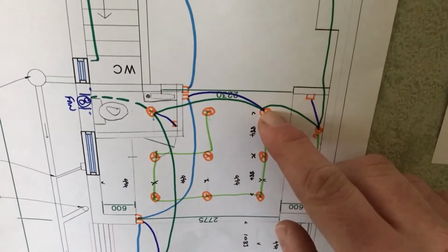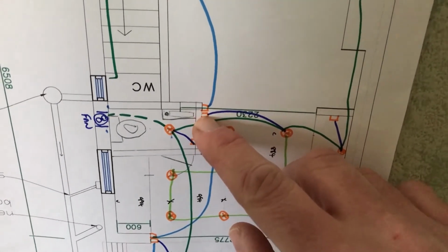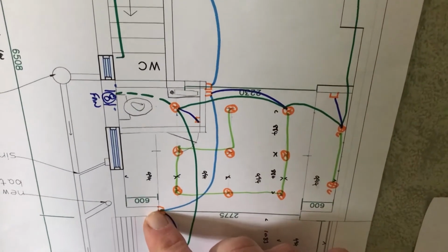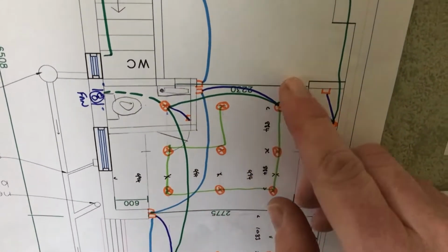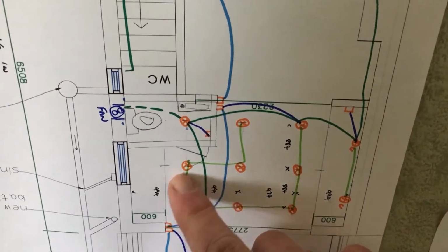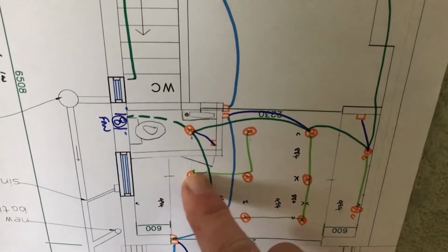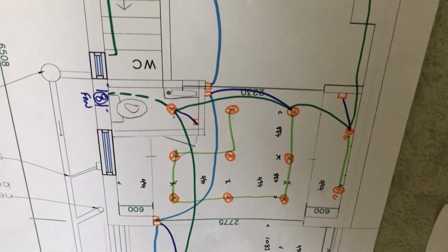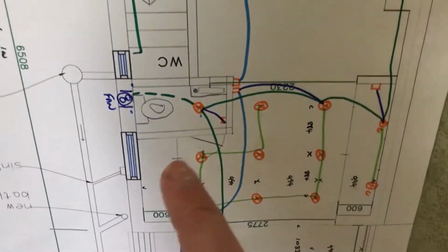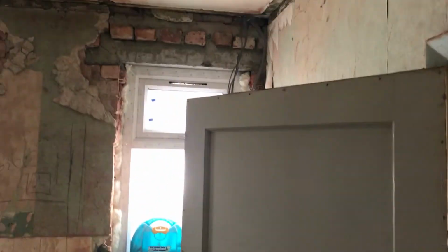Now for the switching, again we need switching going in and out of the room. So we need to bring our 2-core down to the first switch and our 3-core off to the other switch, so we've got two-way switching again. Now because we've got a big bank of lights all connected up on one switch, we need a little switch loop here that connects all the lights when you're switching. Now I said the kitchen's on the bank of 9, it's not really, because the 9th one is actually the toilet.